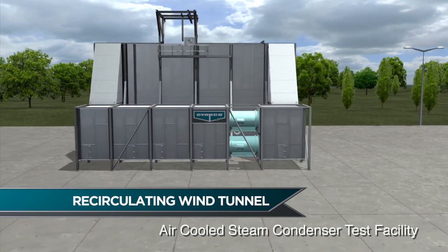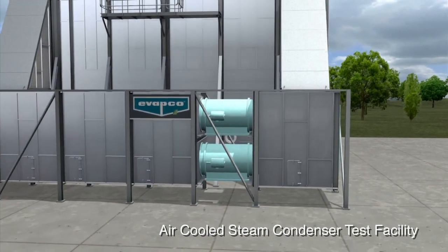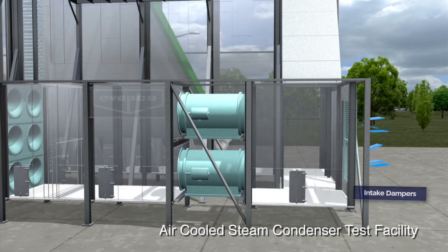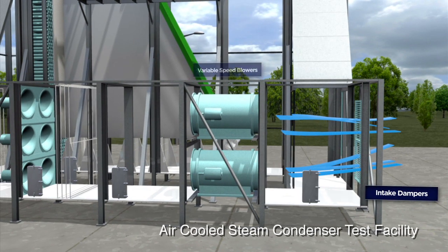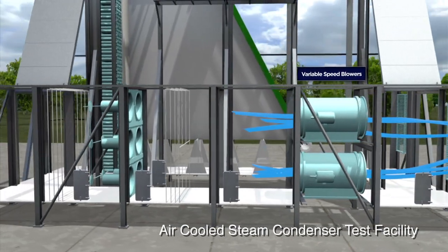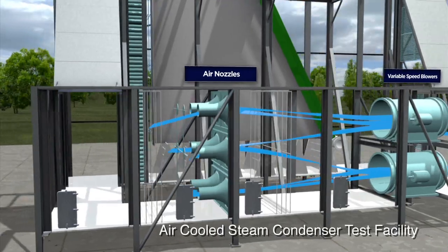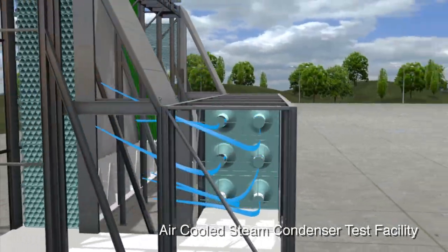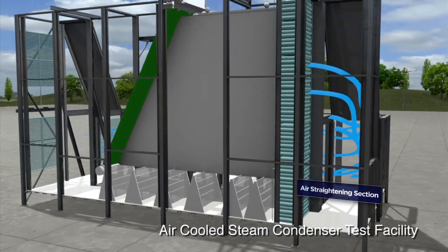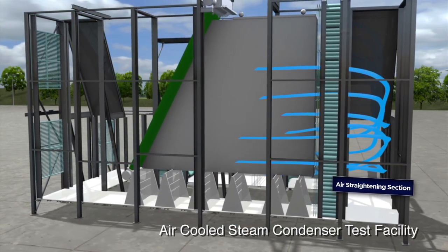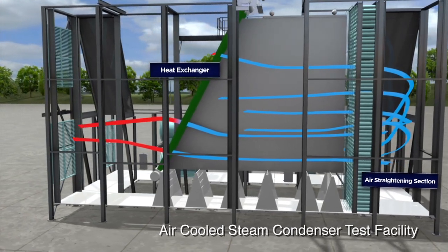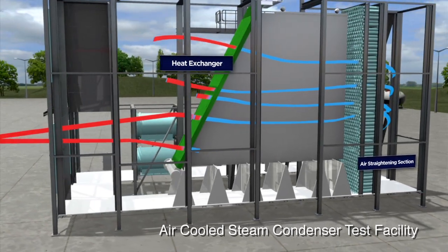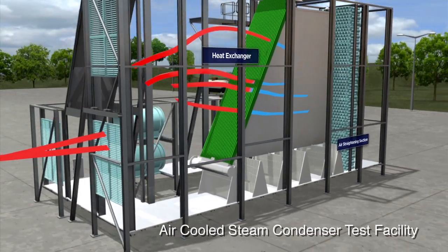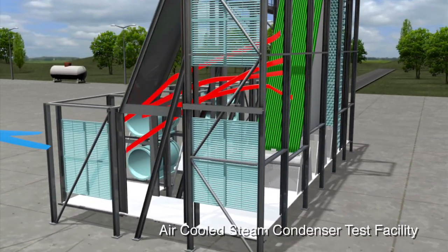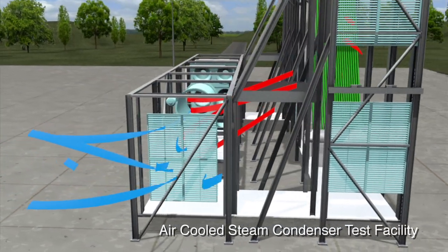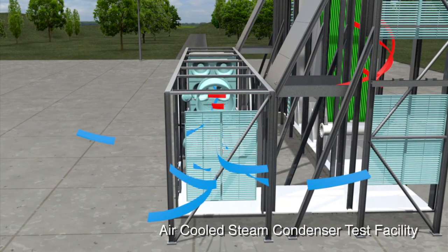A recirculating wind tunnel controls the velocity and temperature of the air supplied to the heat exchanger bundles. Intake dampers allow fresh ambient air to be drawn into the wind tunnel. Two variable speed blowers propel the air around the wind tunnel. The air flow rate is measured accurately through a wall of air nozzles. The air then makes a turn, opening to the tall side of the tunnel, and goes through a series of distribution screens and an air straightening section. The air is uniformly distributed as it approaches the heat exchanger. As it passes through the heat exchanger, the air is heated. The hot air leaving the heat exchanger can be exhausted from the wind tunnel, or it can be recirculated and blended with fresh ambient air to control the air temperature that's circulated back to the inlet of the heat exchanger.